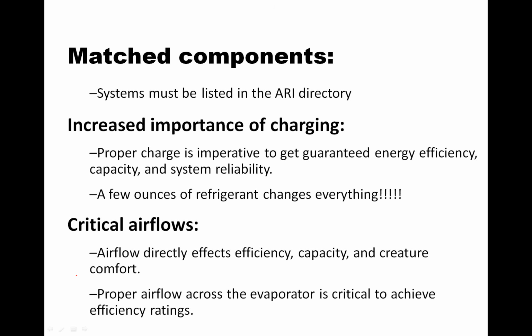And I always get the question: when you're setting the airflow, do you set the airflow to the evaporator size or the condenser size? You always set it to the condenser size, okay? Because in this case, the condenser is going to be the limiting factor, that 2-ton condenser on that 2.5-ton system. And you never want to undersize an evaporator coil. If you undersize the coil, you're going to freeze it up.